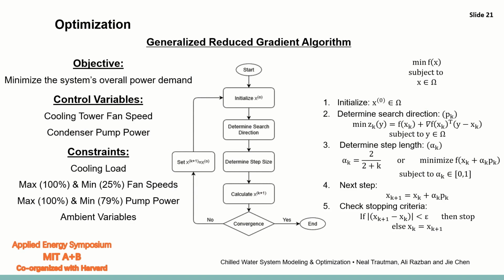So we used a generalized reduced gradient algorithm, which is supposed to be used for smooth, constrained, nonlinear functions, such as the one that we were dealing with. The objective that we set to the optimization was to minimize the system's overall power demand by controlling the cooling tower fan speed and the condenser pump power.